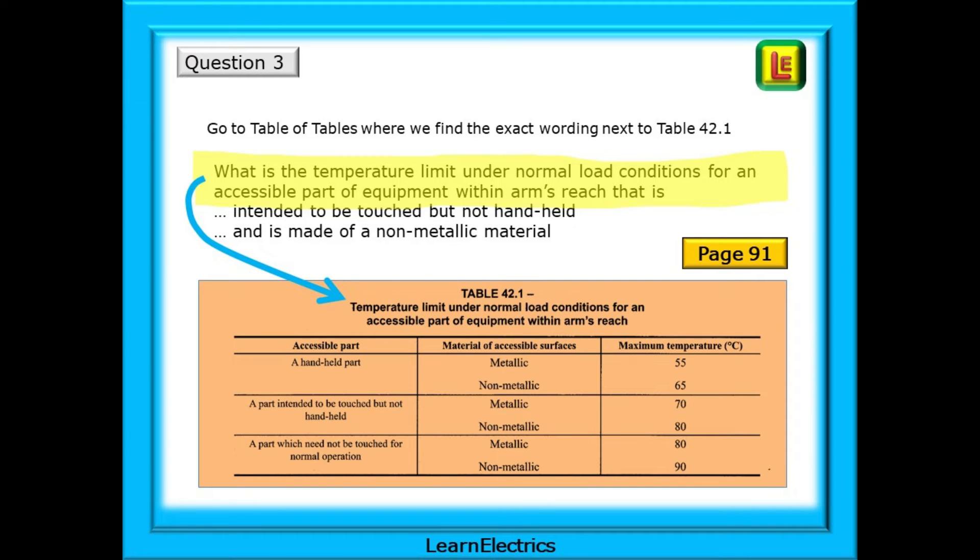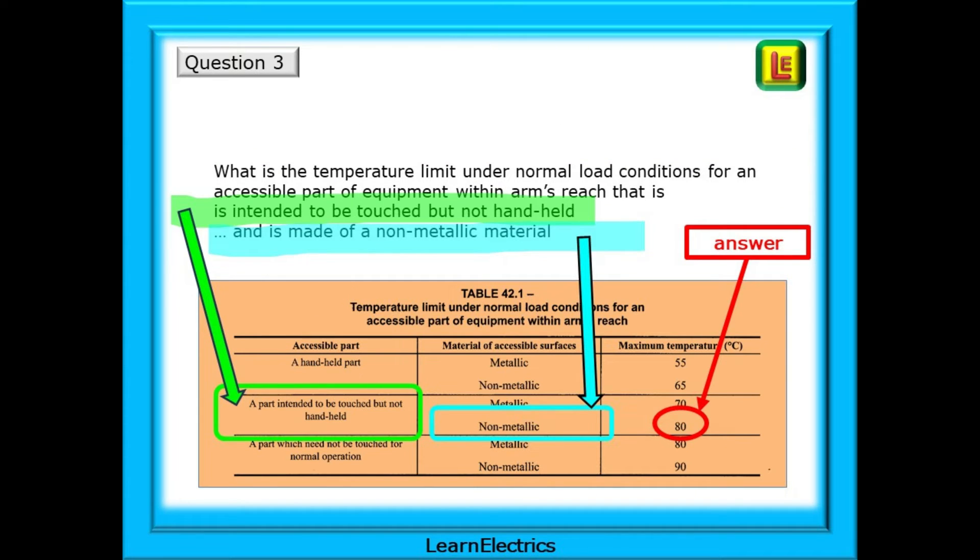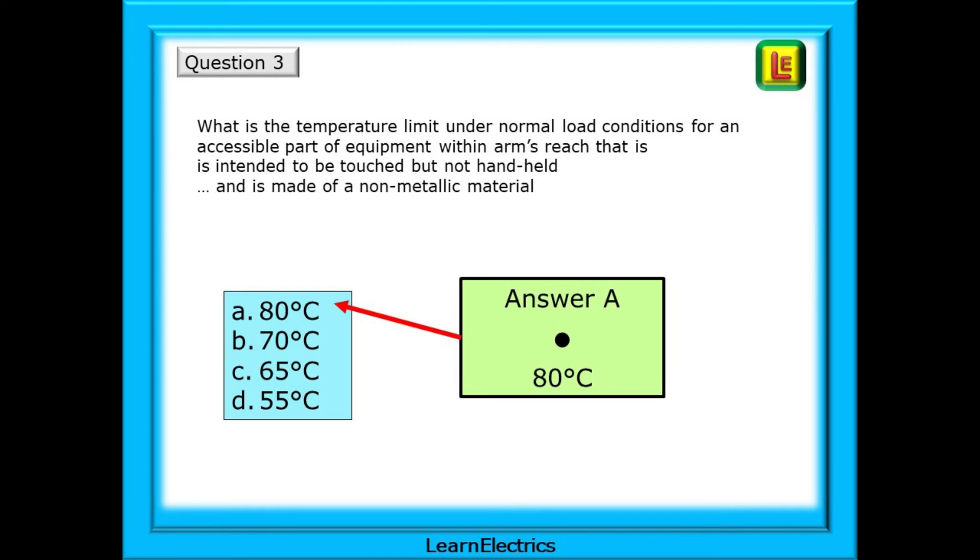Look at the wording of the question, and look at the title of the table. The same words are used. We know that the answer will be in table 42.1. Follow the question. Start with the words, is intended to be touched but not handheld, and follow the green arrow. Then we have the words, is made of a non-metallic material, so follow the blue arrow. The answer must be 80 degrees Celsius. Going back to the answer choices, we have answer A, 80 degrees Celsius maximum.